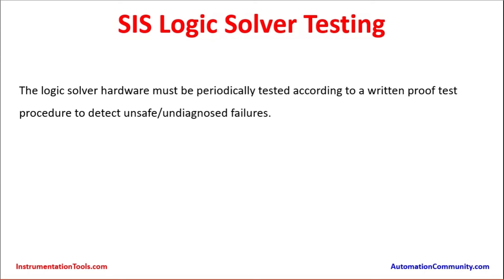The logic solver hardware must be periodically tested according to a written proof test procedure to detect any undiagnosed failures. In a redundant processor setup, two processors run in parallel. During shutdown, one processor can be made idle while the second takes over all control. Once everything is re-established to the prior condition, the second processor can be switched back for the first to take over. Because the logic solver is a vital and critical part of the Safety Instrumented System, it must work perfectly for the total system to perform well.